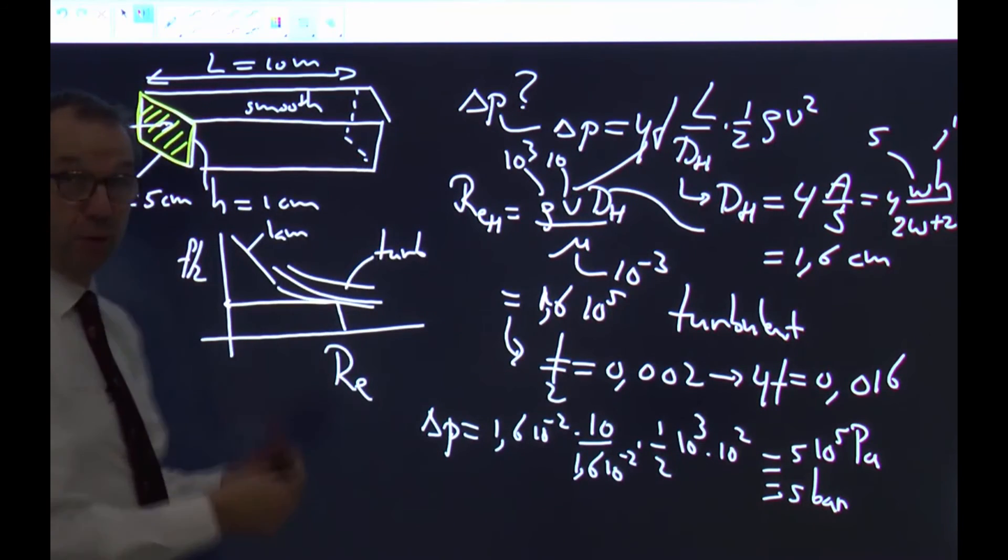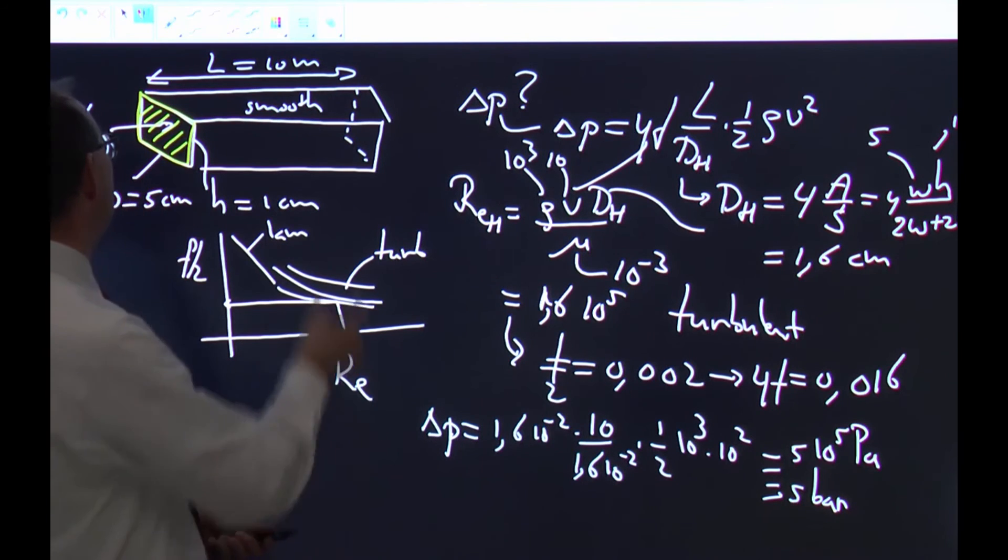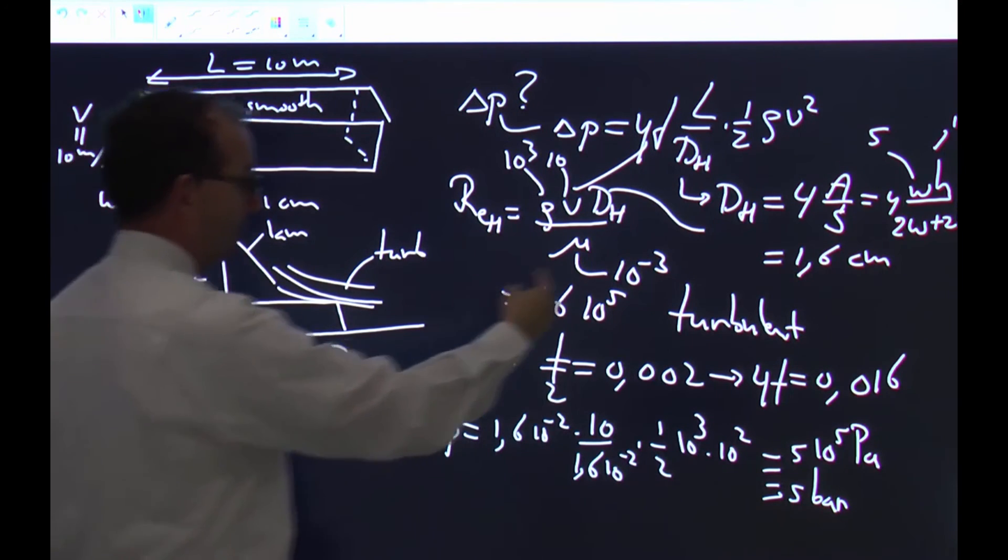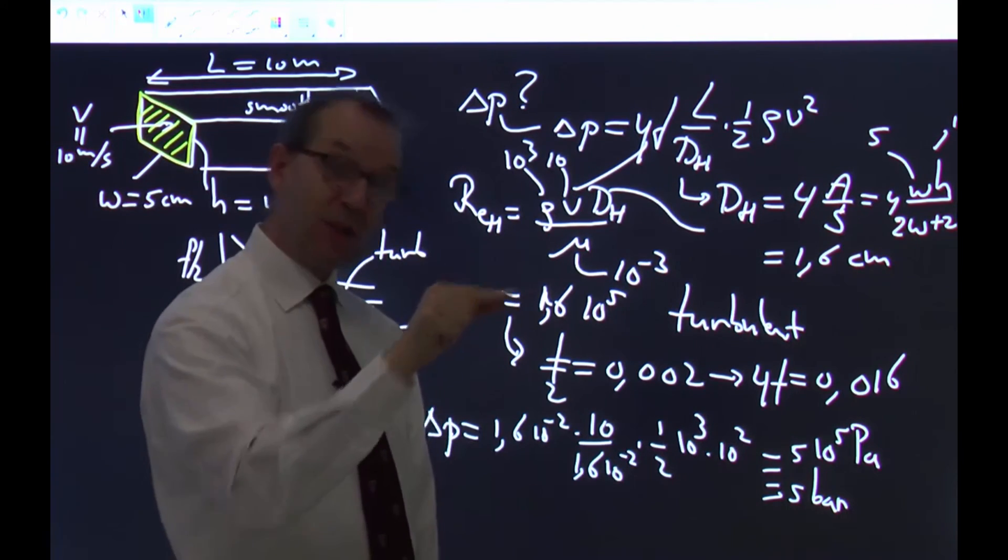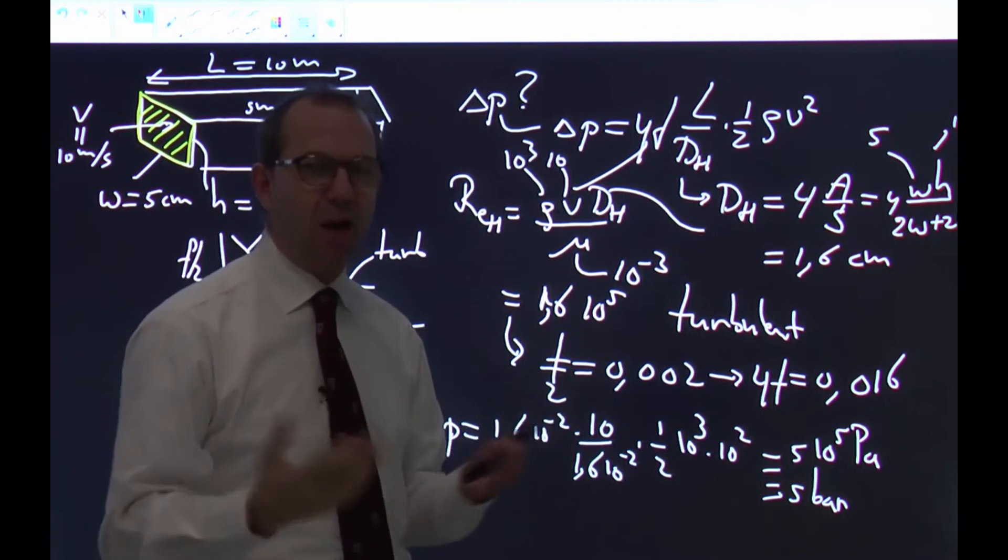So there's quite a pressure drop over the 10 meter, and that is due to that actually the duct is narrow, as if it's a tube of 1.6 centimeters, less than an inch, and I flow at 10 meters a second through it, which is pretty high velocity.